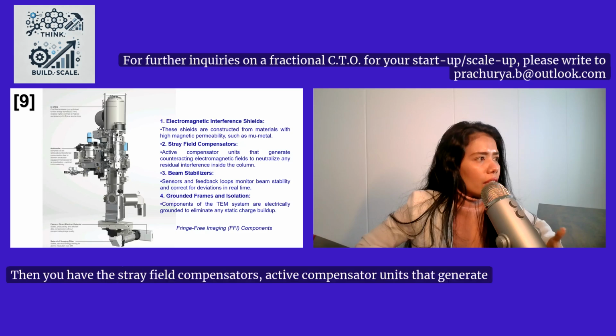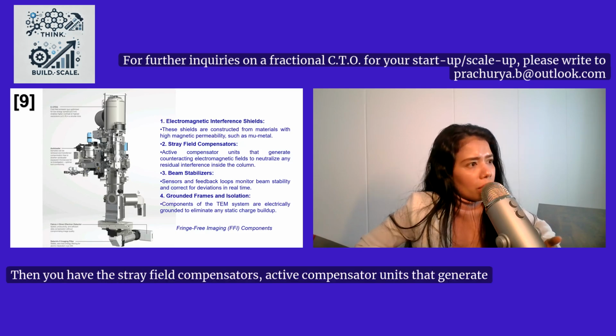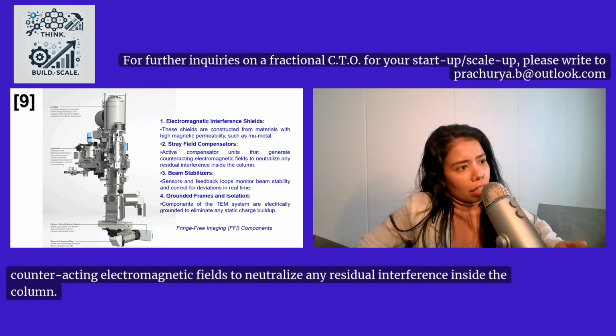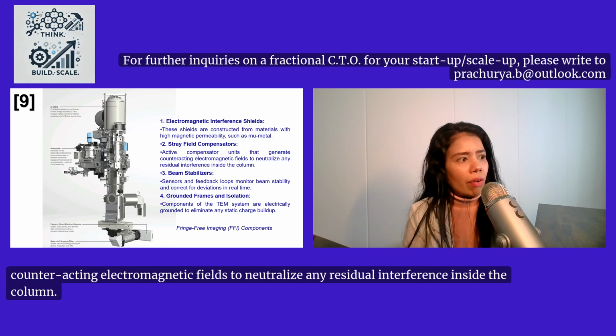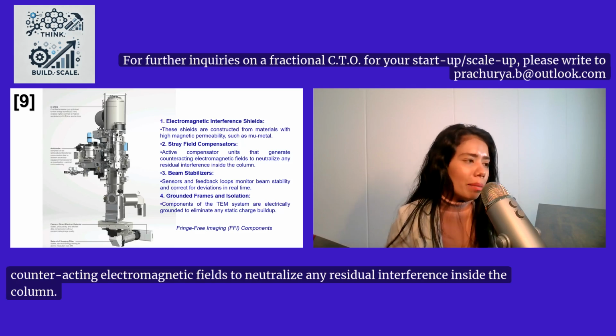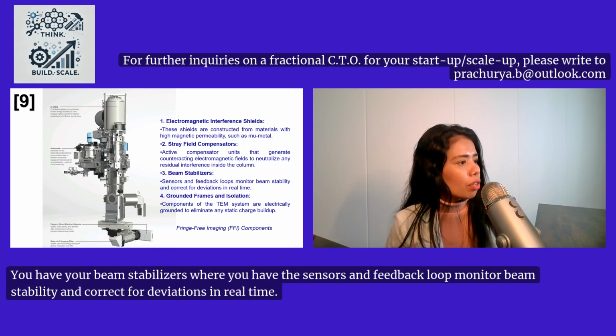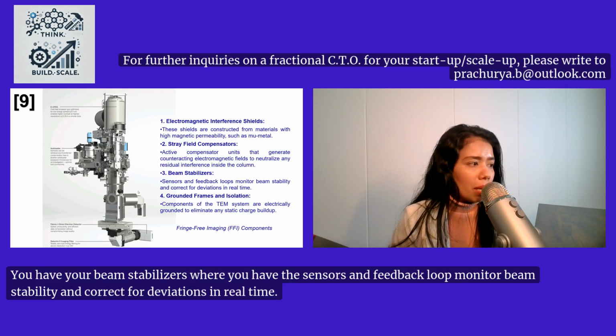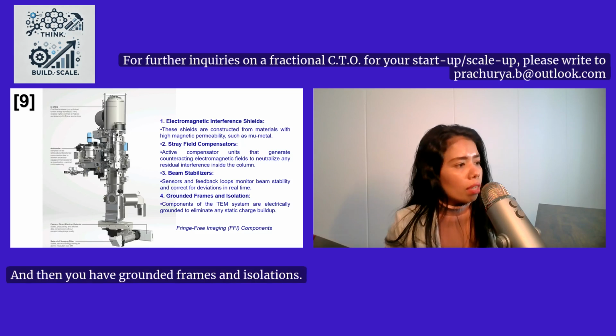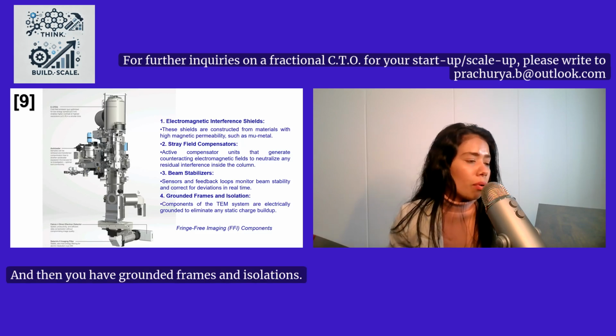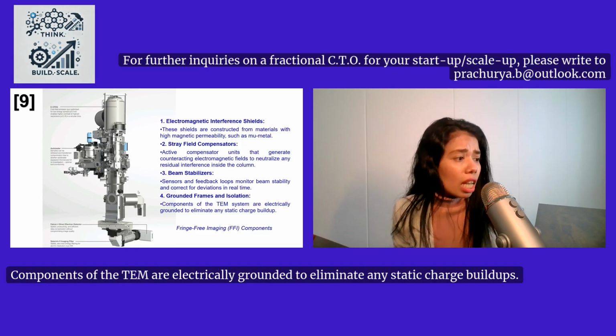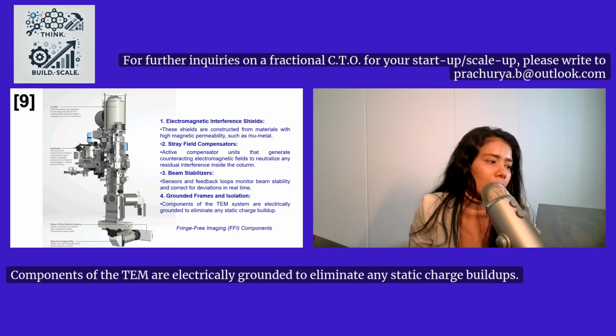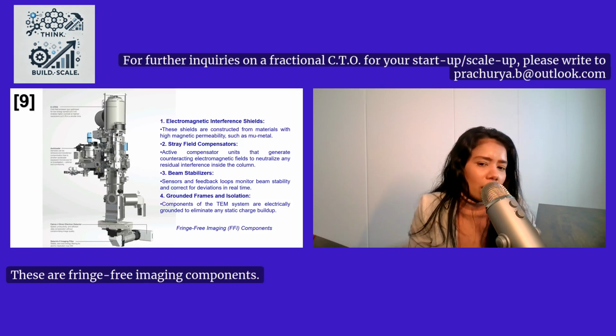Then you have the stray field compensators, active compensator units that generate counteracting electromagnetic fields to neutralize any residual interference inside the column. You have your beam stabilizers, where sensors and a feedback loop monitor beam stability and correct for deviations in real time. And then you have grounded frames and isolations. Components of the TEM are electrically grounded to eliminate any static charge buildup. So these are fringe-free imaging.